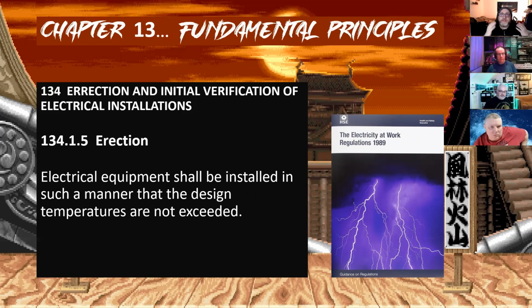Quite often a designer may have some assumed design temperatures rather than specifics. A designer shouldn't say it'll run exactly that temperature, but give a range. But the installer may have an alternative method of installation that the designer didn't quite identify, or there could be another characteristic. It's very easy for the initial planning of a design to end up being installed differently, with the actual temperatures of the system ending up different due to many external influences. Understanding the design temperatures at the beginning, middle, and end phases is quite important, but it's not really something we look for when we inspect.